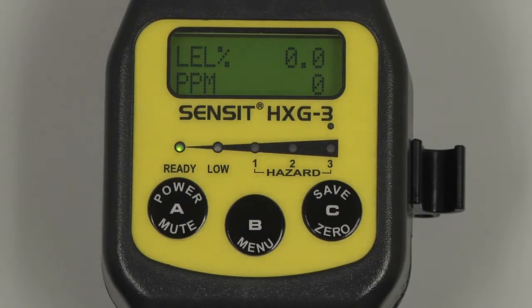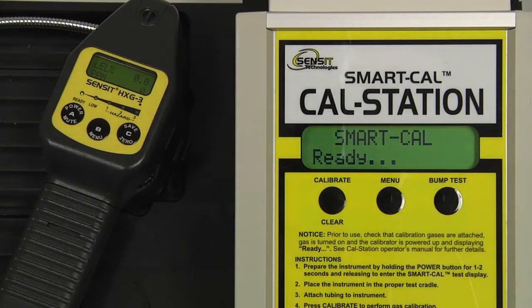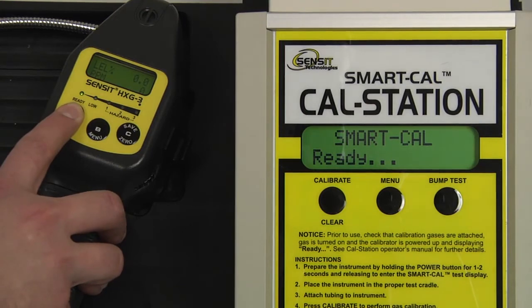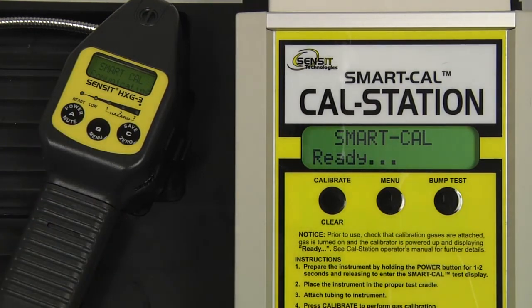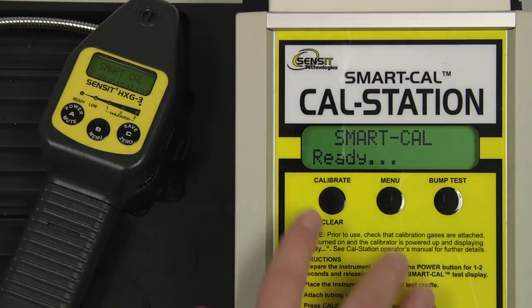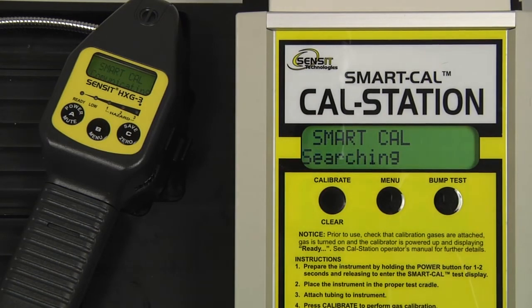Allow the instrument to warm up for an additional 5 to 10 minutes before calibrating. To begin, place the instrument in the cradle of the cal station, attach the instrument hose to the end of the gooseneck, and enter into Smart Cal mode by pressing and holding the A button for 1 to 2 seconds. Press and release the calibrate button on the cal station, and the process will begin.